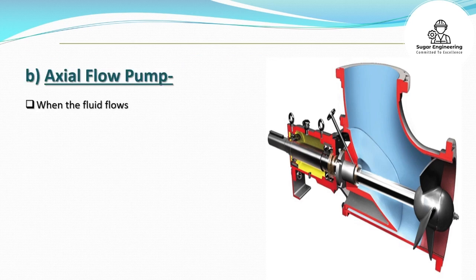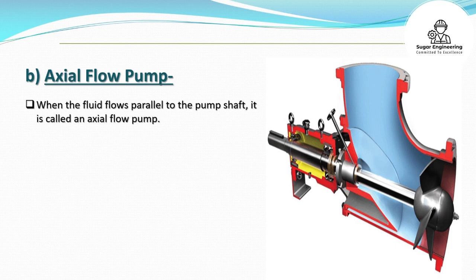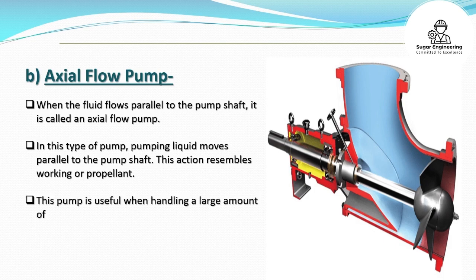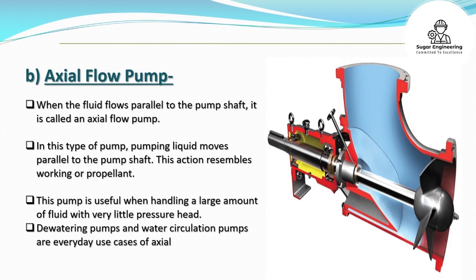B. Axial flow pump. When the fluid flows parallel to the pump shaft, it is called an axial flow pump. The pumping liquid moves parallel to the pump shaft, resembling the working of a propeller. This pump is useful when handling a large amount of fluid with very little pressure head. Dewatering pumps and water circulation pumps are everyday use cases of axial flow pumps.